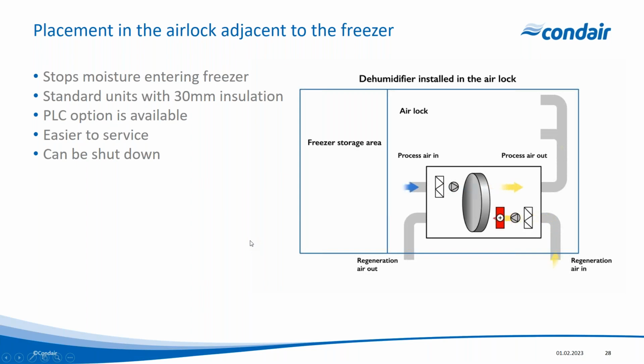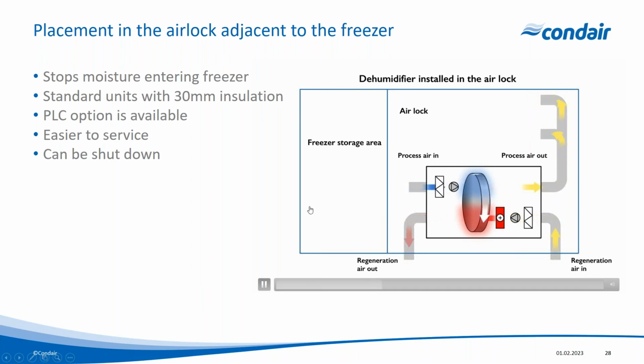There is another option though. You could, if you've got an adjacent chill store, mount the dehumidifier inside the chill store. Now this is quite a nice way of doing it, because we can put the dehumidifier in the chill store and actually dehumidify the air in the chill store. So here, if you can imagine on this drawing, we've got the freezer store area, and then perhaps we've got a production area, or we've got a chilling area. So a freezer store maybe at -27, -28, and chill store, let's say 1-2 degrees C. Well, here we're taking process air in from the chill store over a filter and a fan. We're drying that air and then sending it back into the chill store.